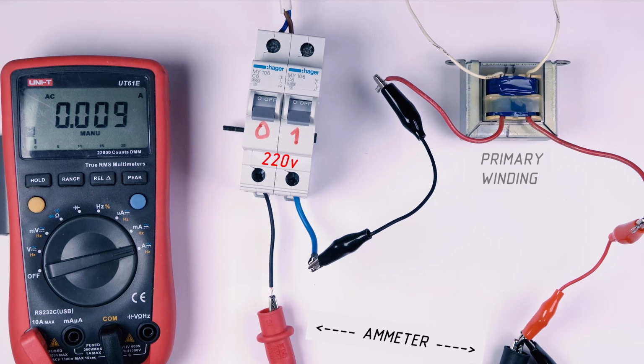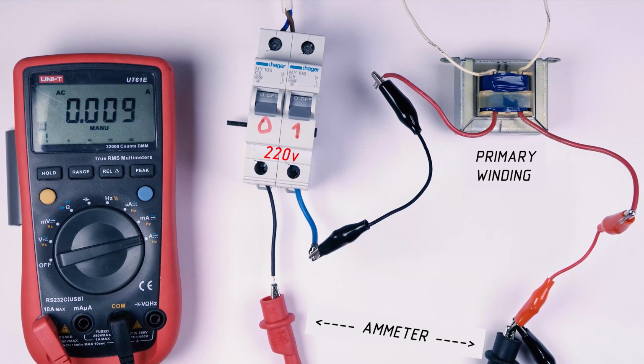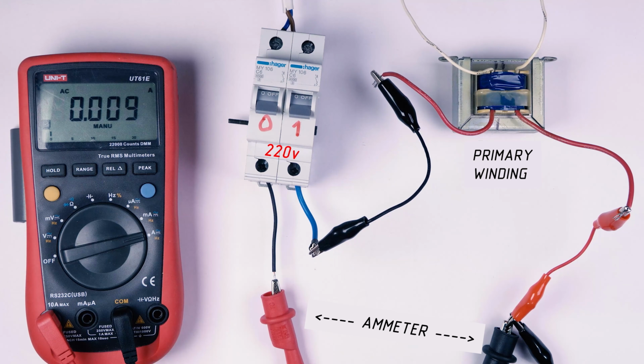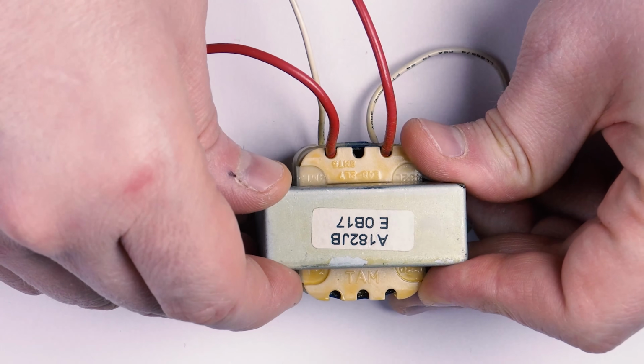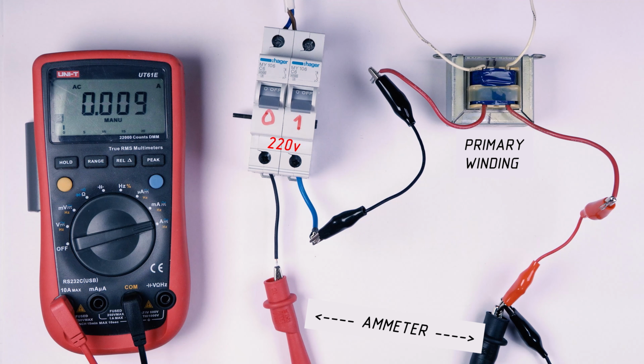Let's start with a simple test. We'll measure the current flowing through the primary winding without load, also called the idle current. This will help us understand whether the transformer is rated for 220 volts. If the current is too high, it obviously means that it's not.